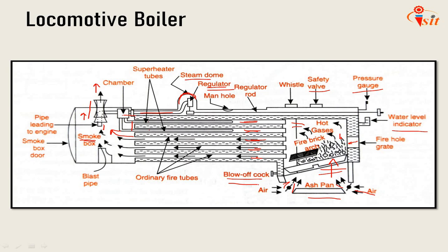Demerits are: there are chances of corrosion and scale formation in the water legs due to the accumulation of sediments and mud particles, some water spaces are difficult to clean, large flat surfaces need bracing, it cannot carry high overloads without being damaged by overheating, and there are practical construction limits for the pressure and capacity, which do not meet the requirements.